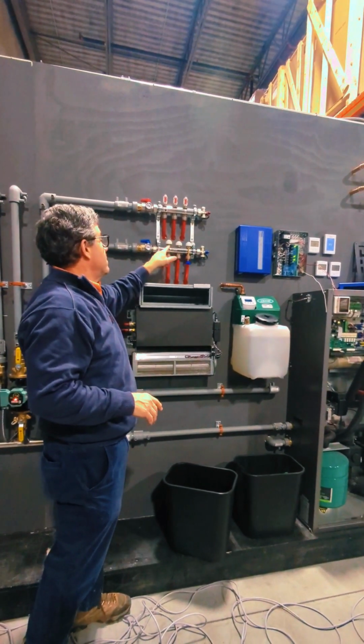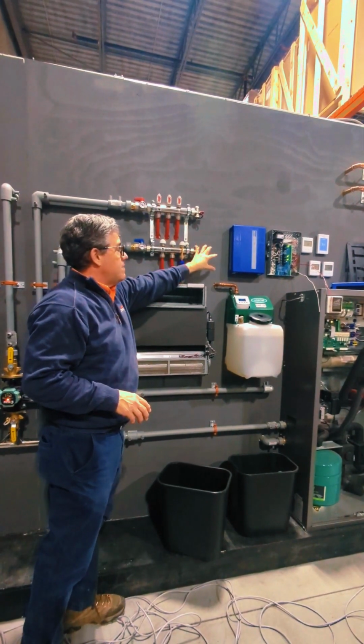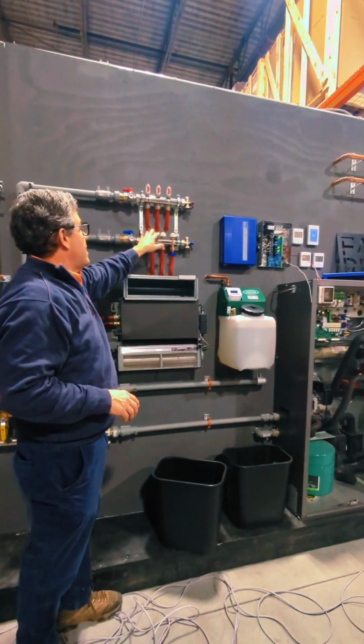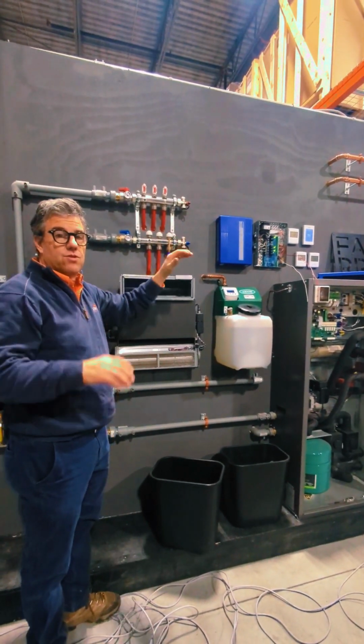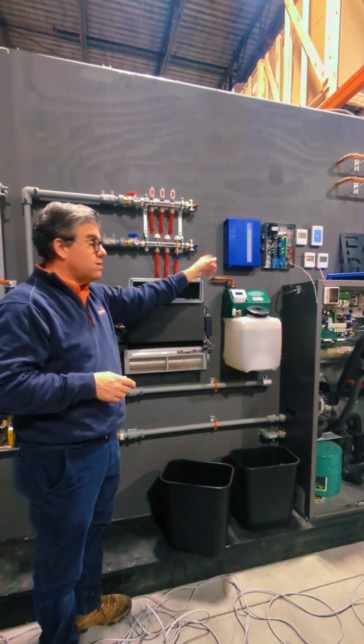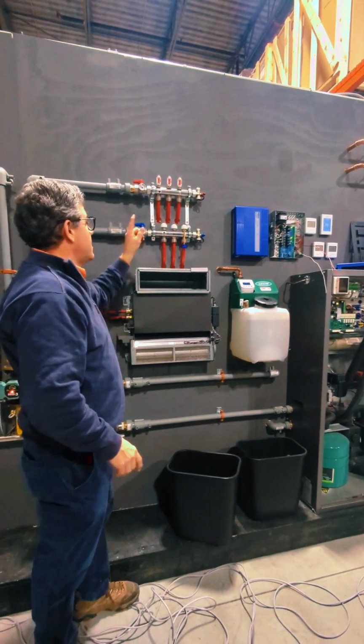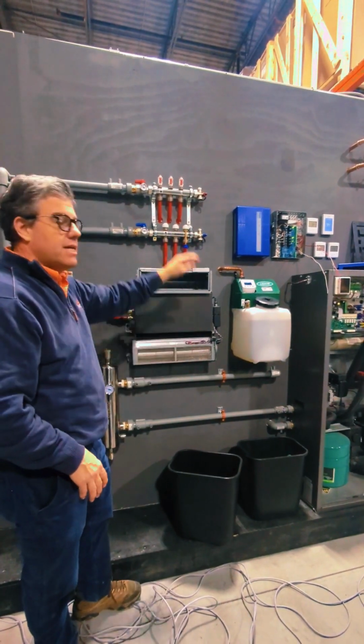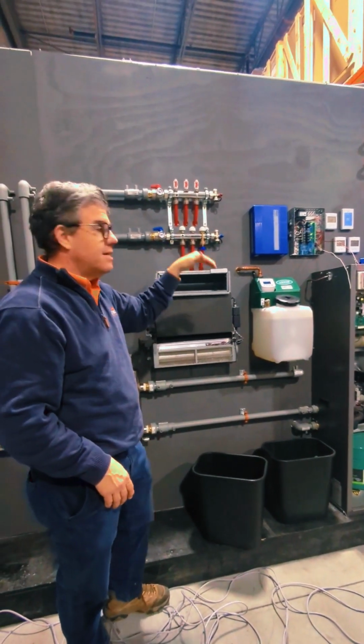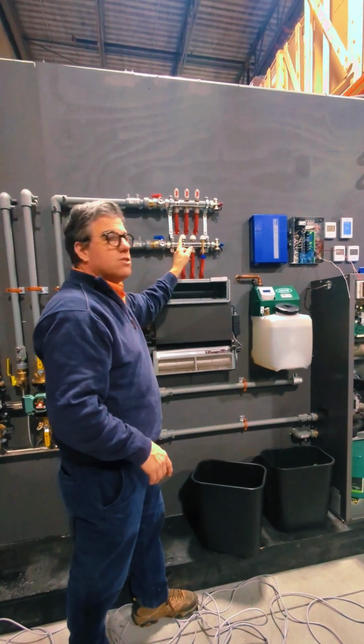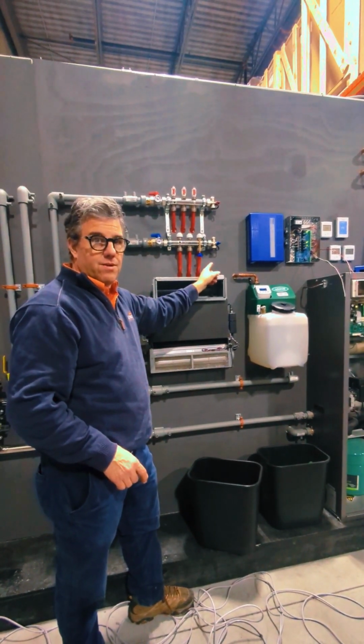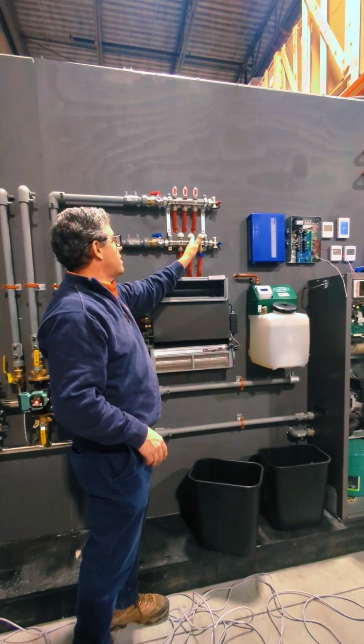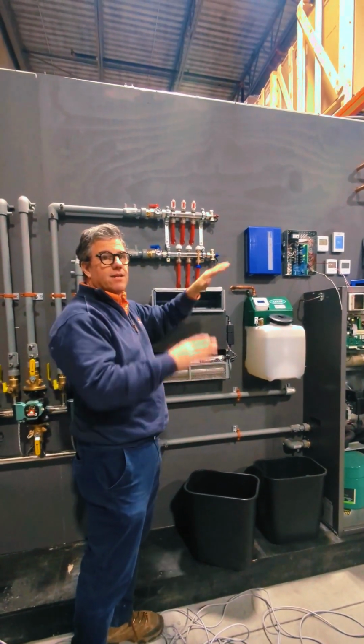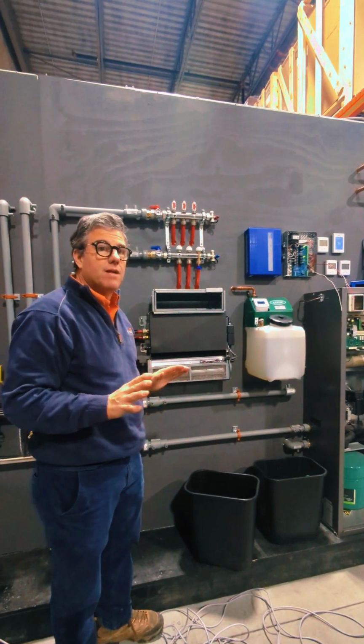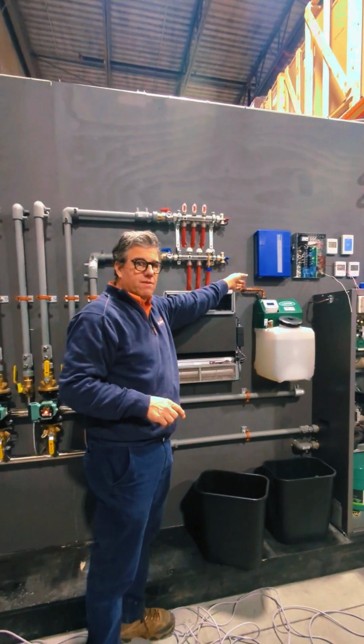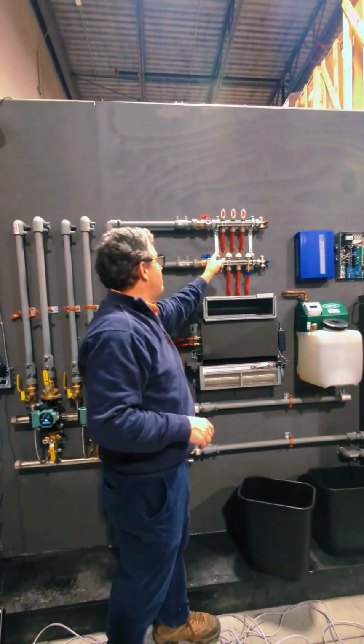What that allows is the meter to be the master, and the valves are all slaves to that master. So we run a sequence that the meter starts — with the pump running, each valve opens independently and then closes. The meter remembers each zone's flow, so it knows this is 2.6, this is 2.8, this is 3.1, this is 1.9. That way it can balance the whole system dynamically, since it has a measurement value for flow and a valve position.